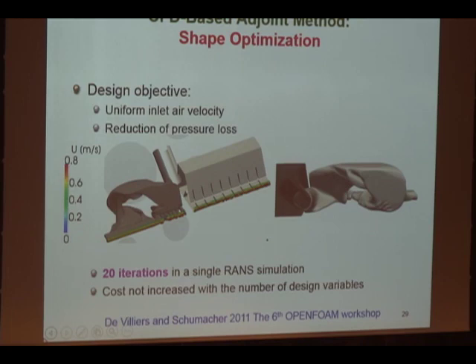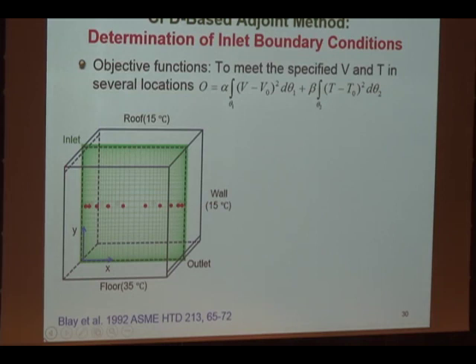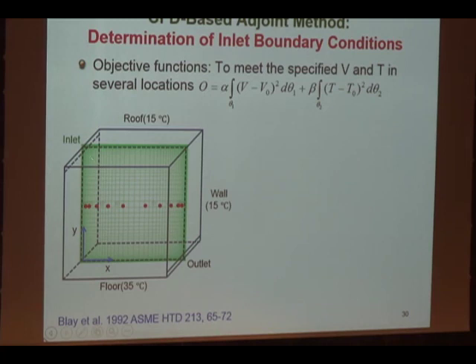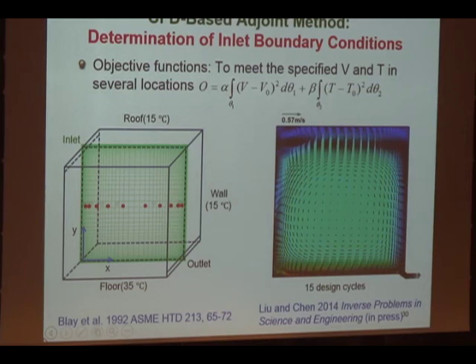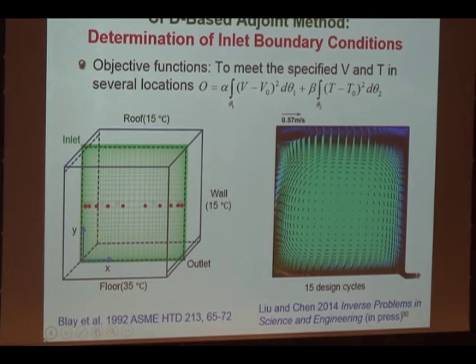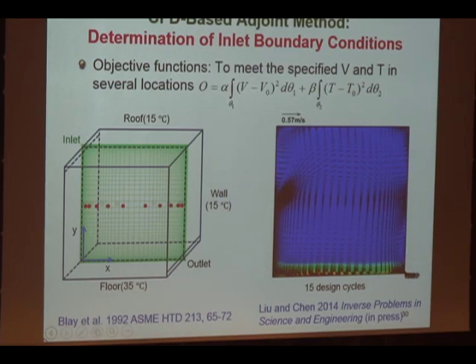We can also look at building cases. A simple case like Peter just showed — an inlet, an outlet, and I want exactly the same velocity and temperature as measured data at a few points along a line. Can I recover the inlet velocity? Starting with some arbitrary initial velocity and temperature, the process automatically converges. The final result of the inlet position is close to the real one on the top, but not exactly the same. So inverse modeling is possible. For a more complex case — a half cabin, first class, one row — my design objective is to make PMV equal to zero throughout the pink area around the occupant.